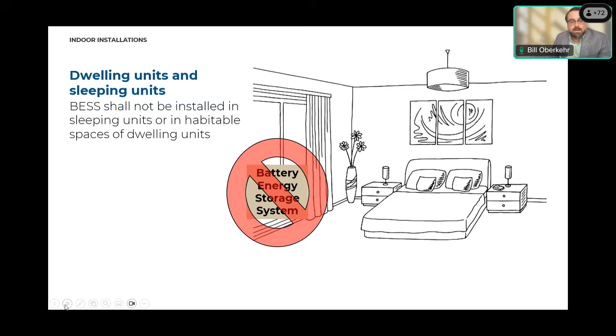For rooms and areas containing energy storage systems, this is the fire resistance rating requirement. We need the system protected by no less than 5/8 inch type X gypsum board or the equivalent. That is written out in R330.4 for more detail, and again, that does include the ceiling. Another one that is perhaps common sense to most folks, but in the event that it's not: no energy storage systems in dwelling or sleeping units. Hard and fast rule there in the residential code.